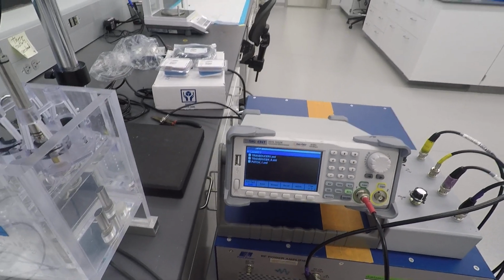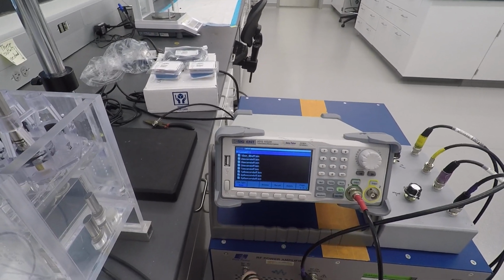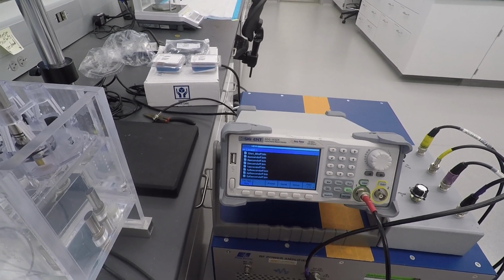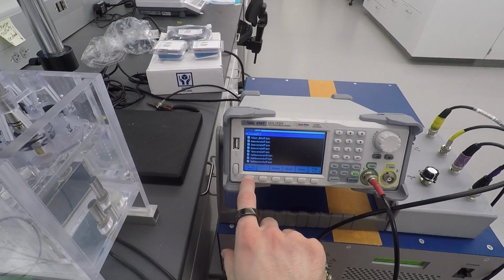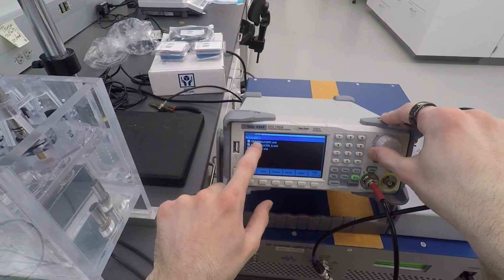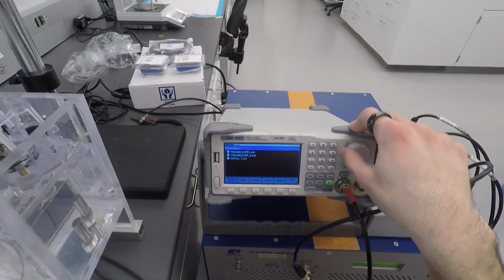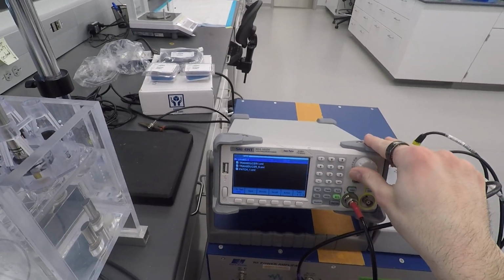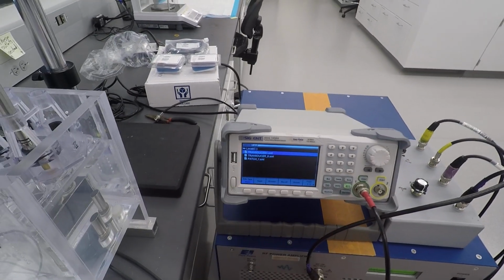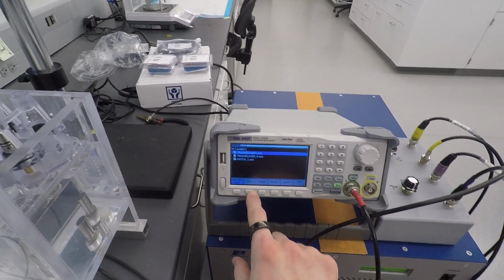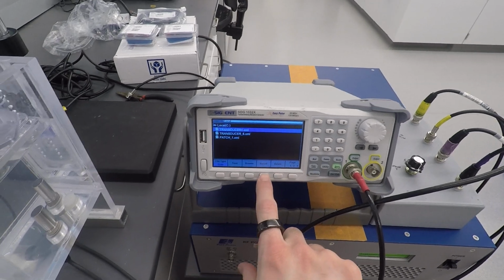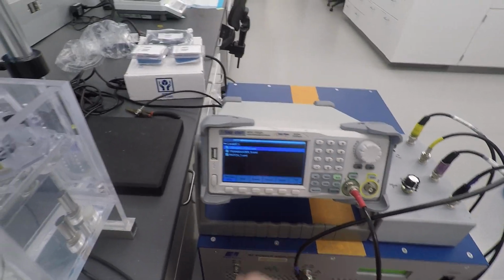You'll see a screen like this pop up. Normally you'll see local files, which are not what we want for this case. Those are preloads. We want to change our file type down here to state. So once that's up, you'll see transducer 1, transducer 5, patch 1. That just refers to whether it's 1 or 5 megahertz. So we'll use our scroll wheel over here, scroll down to transducer 1, and then we'll press recall right here in the middle by pressing this button that says recall.